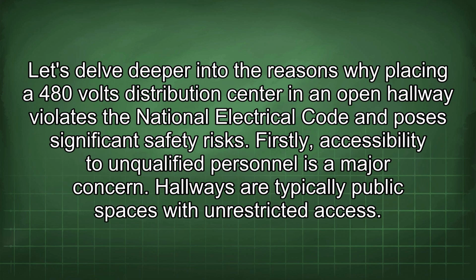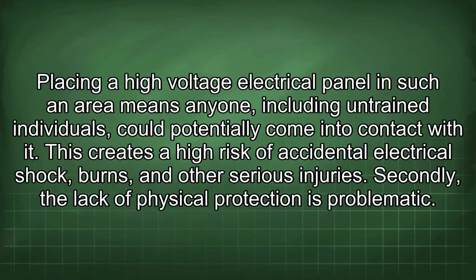Let's delve deeper into the reasons why placing a 480 volts distribution center in an open hallway violates the National Electrical Code and poses significant safety risks. Firstly, accessibility to unqualified personnel is a major concern. Hallways are typically public spaces with unrestricted access. Placing a high-voltage electrical panel in such an area means anyone, including untrained individuals, could potentially come into contact with it. This creates a high risk of accidental electrical shock, burns, and other serious injuries.